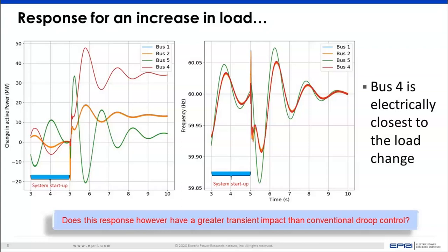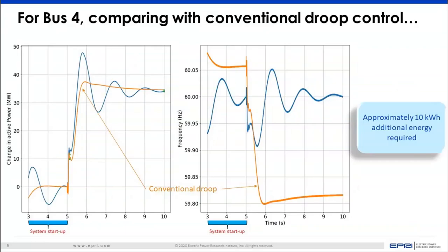So here, bus 4 was electrically closest to the disturbance, which is why that resource responds more, as is typical in a distributed slack bus scenario where electrical distance plays a huge role. How much additional energy it provides can be easily compared when you compare conventional Droop frequency response, as shown here by the orange curve, and our constant frequency control, as shown by the blue curve.